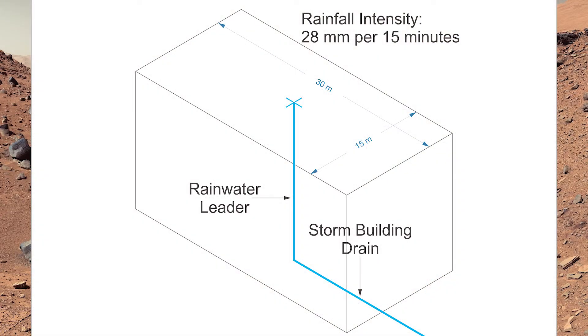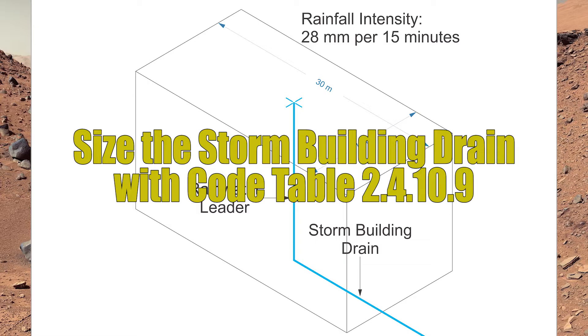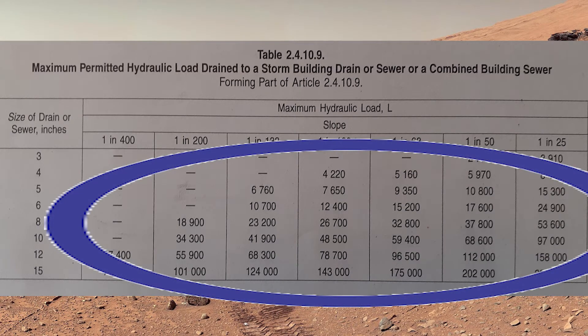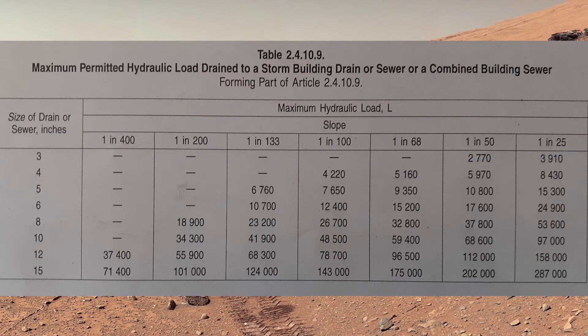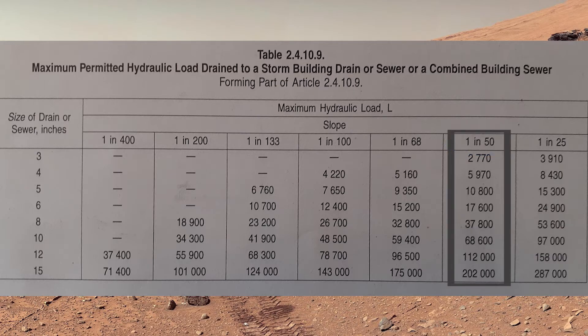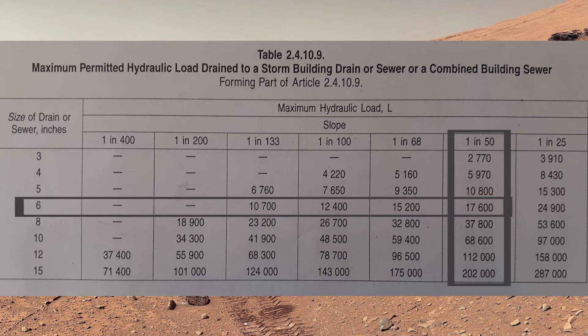As the rainwater leader travels down, it's going to turn a hard right to a horizontal pipe that we call the storm building drain. We'll need to reference table 2-4-10-9 to size that. We're going to see a whole bunch of liter values and a bunch of slopes, so I need to know the slope or grade of the pipe. I select 1 in 50, which is about quarter inch per foot, and go down the list. I notice there's 10,800 or 17,600 — 10,800 is not enough, so I go to 17,600, go across to the left, and find out the size of my storm building drain needs to be six inches.